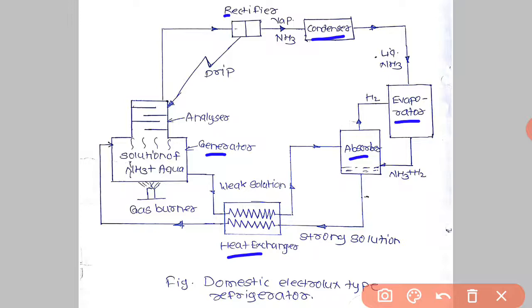Now see the working of this type of refrigerator. The strong ammonia solution from the absorber, through the heat exchanger, is heated in the generator by applying heat from an external source. Here we used a gas burner. During the heating process, the ammonia vapors are removed from the solution and passed to the condenser. See here, NH3 vapors are passed to the condenser. A rectifier or water separator is fitted before the condenser, and it removes water vapors carried with the ammonia.